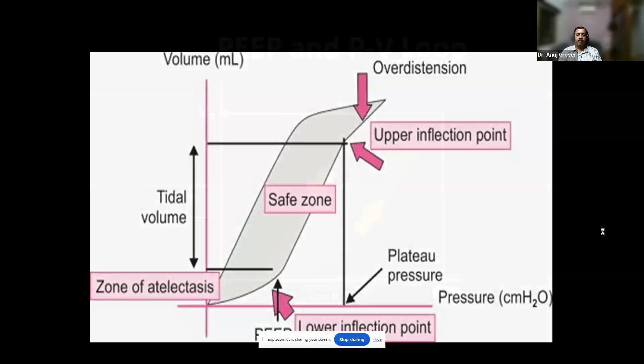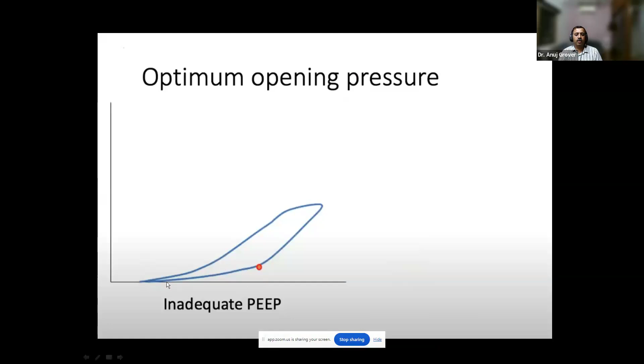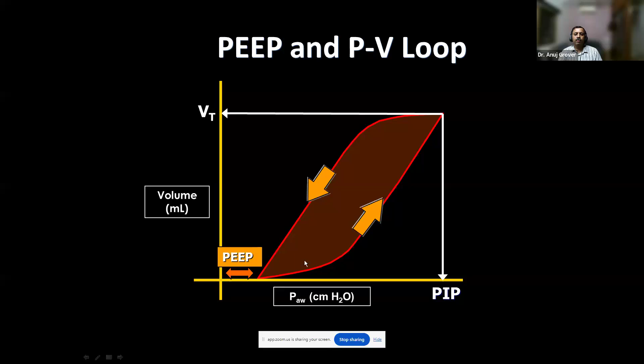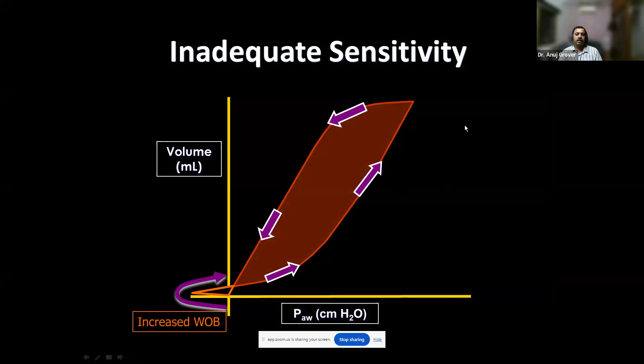When you add PEEP to the PV loop, the loop shifts a little bit to the right. This is the baseline pressure that you're starting at. If your PEEP is inadequate, the loop doesn't rise much, so your lower inflection point is much towards the right. In this case, if the PEEP is set at 2 to 3, you need to keep the PEEP around 5 or 6 so that you get this kind of a graph. If you kept the sensitivity inadequately, the baby has to work harder, so the negative inflection point goes even more towards the left. The more it is towards the left, the harder the baby has to work to trigger the breath. So make sure this is not going too much towards the left.